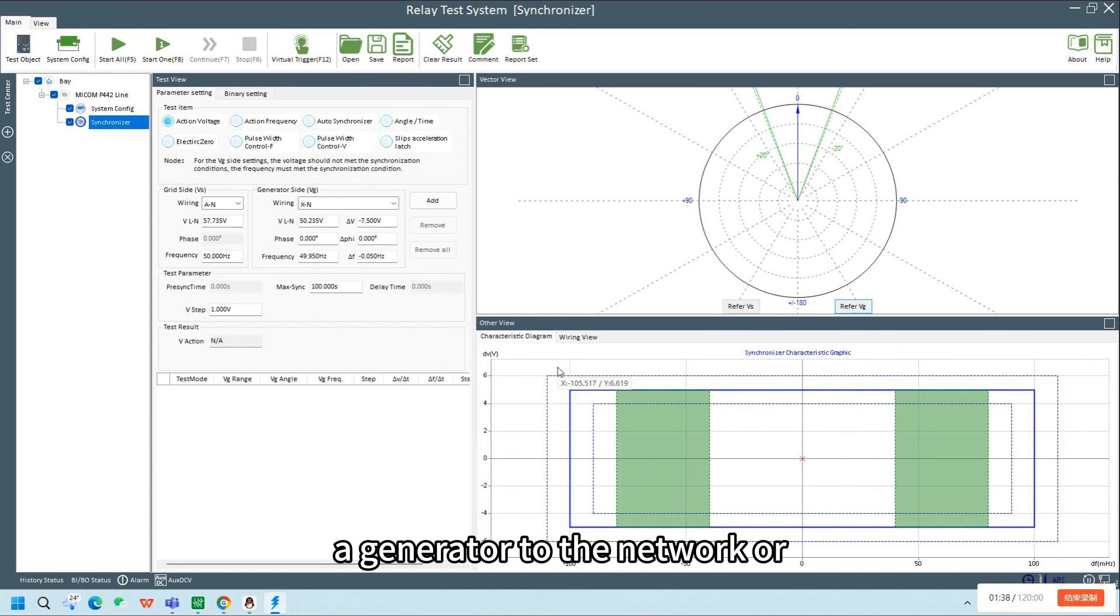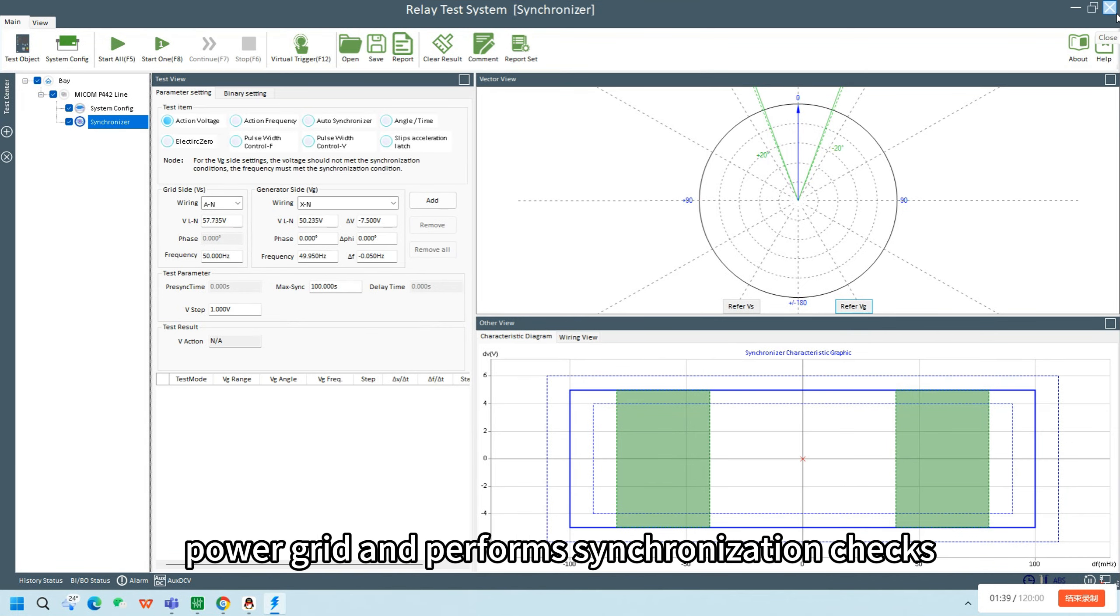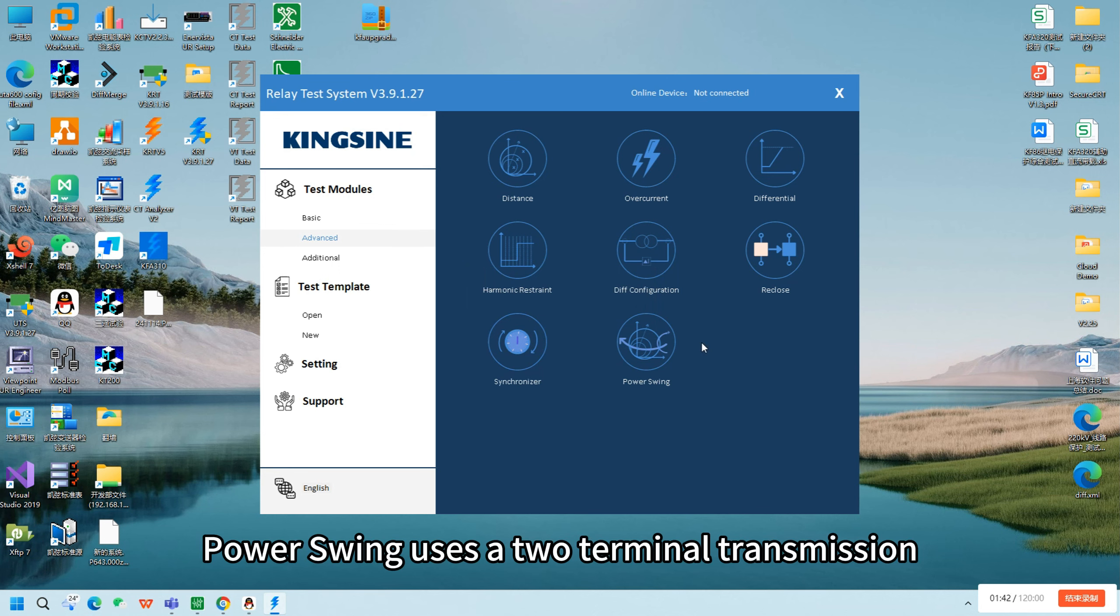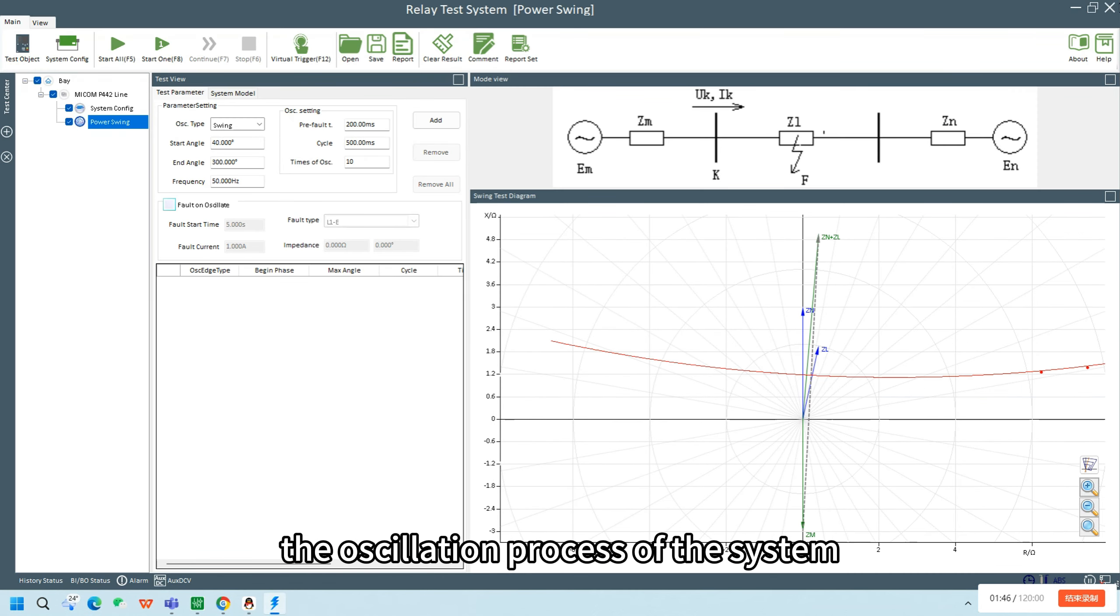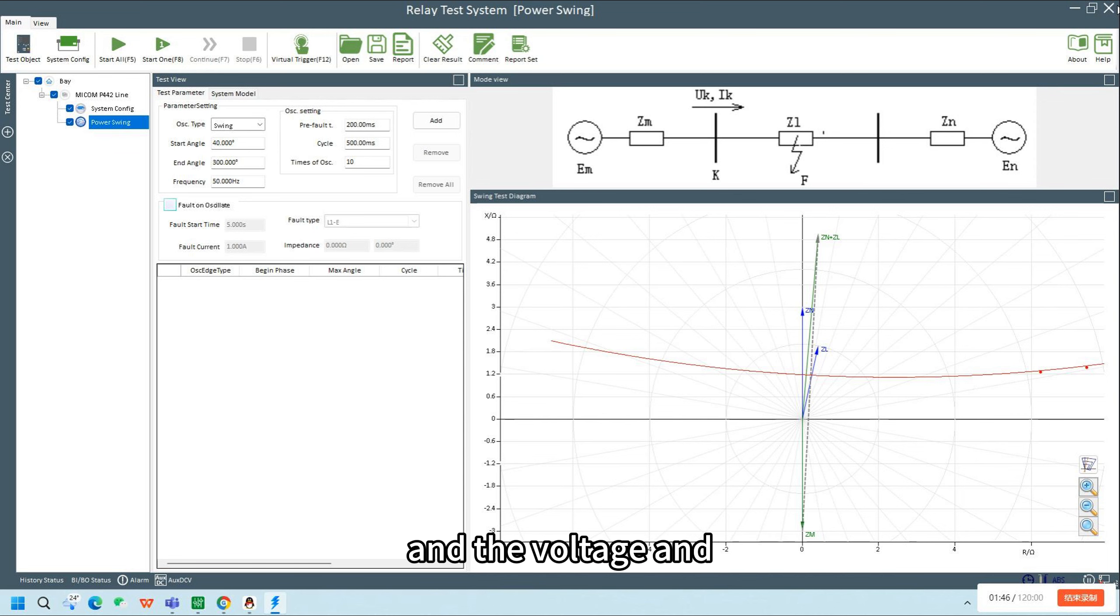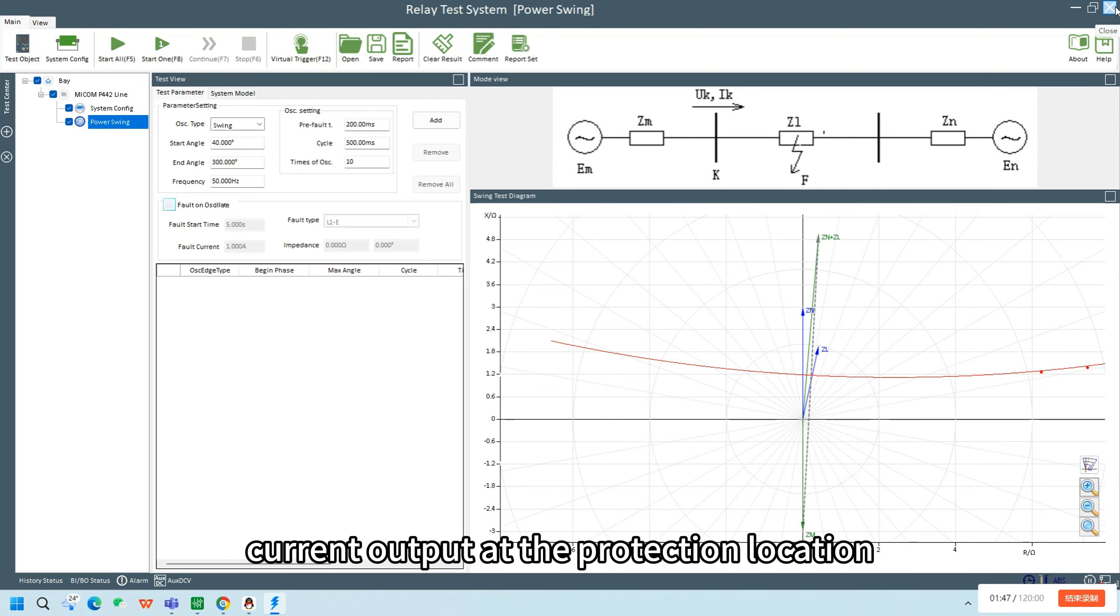Synchronizer is a module that simulates connecting a generator to the network or power grid and performs synchronization checks. Power Swing uses a two-terminal transmission system model to simulate the oscillation system process and the voltage and current output at the protection location when a fault occurs during the oscillation.